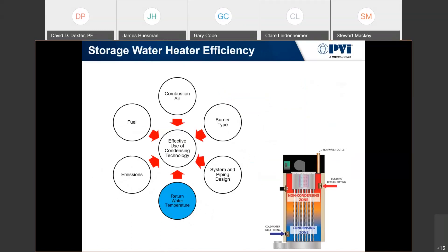Return water temperature is the most important factor in judging efficiency. Looking at that mid-body return fitting, we're bringing back the building return — at a higher temperature than cold water — into a non-condensing zone of that condensing water heater. In situations where the building only sees 3 GPM, we're not preheating that 3 GPM feeding the heater. The only water we're actually feeding that water heater is as cold as possible, which means our efficiency curves are much flatter.